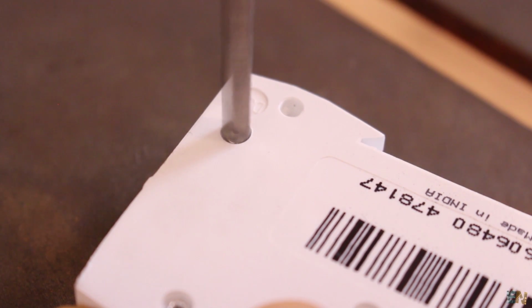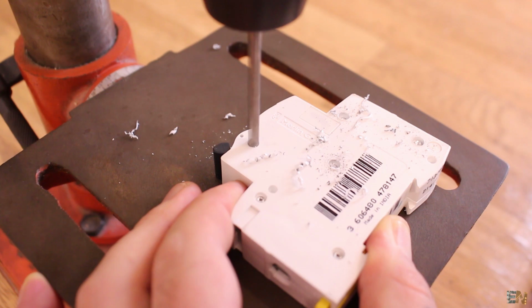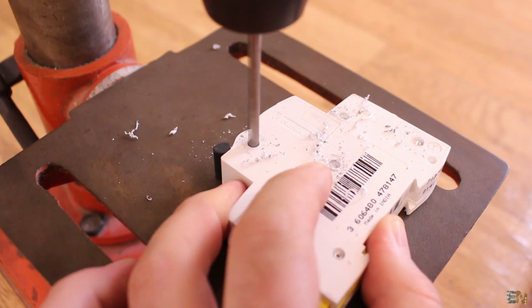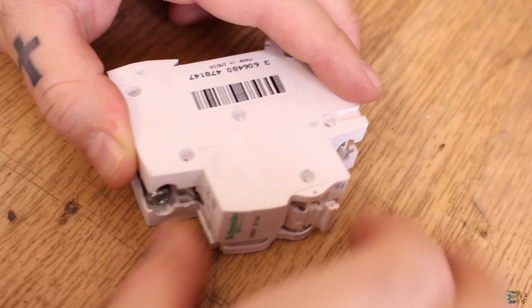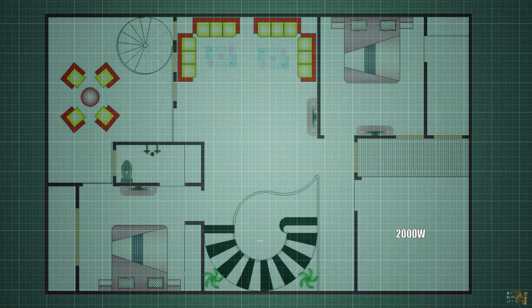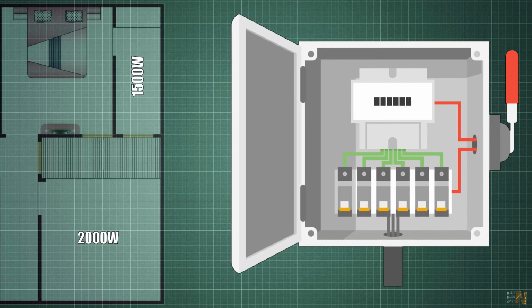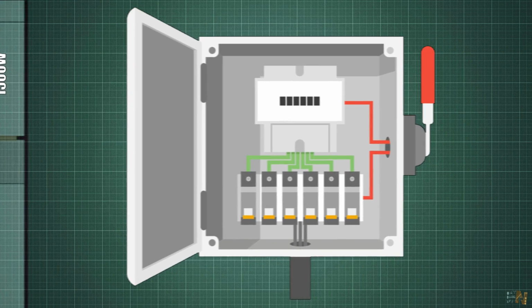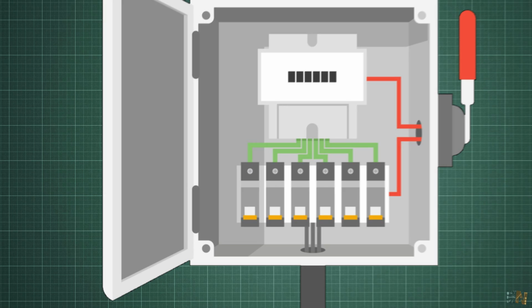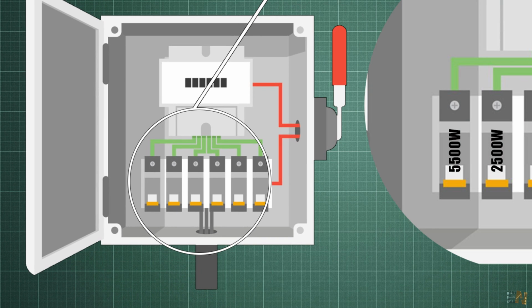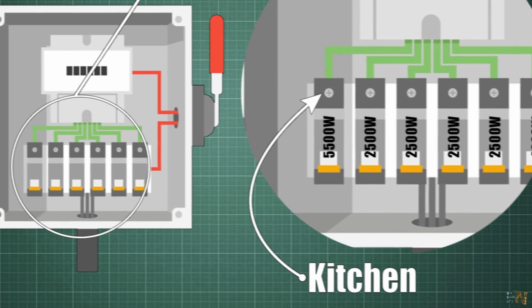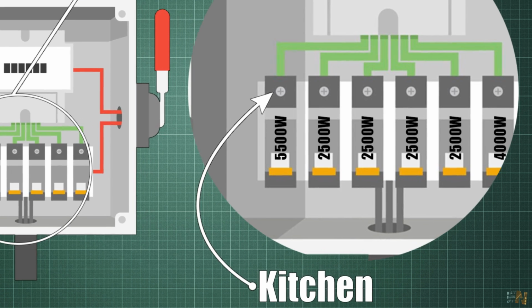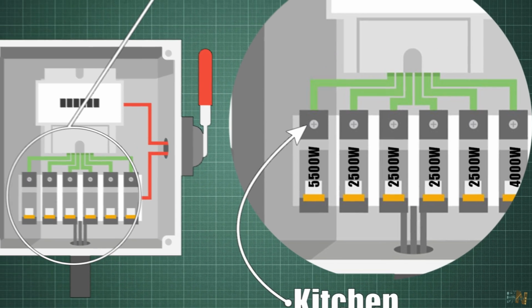Well, for that we need to open this one and see what we have inside. So stay tuned for that. But first, what is an overload? Well, to protect our homes, each room or small sector is limited to a certain power. Let's say 2000 watts. You will see the electric panel with different breakers for different rooms or sectors of your home. Usually kitchens with electric heaters, boilers, ovens and so on would be rated to a higher power or have a separate breaker just for that high power heater.